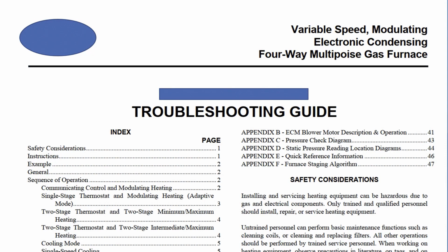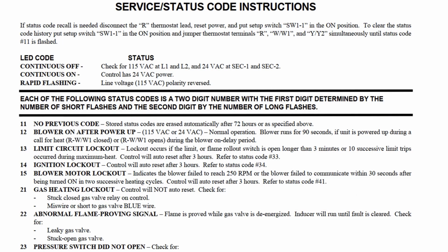Let's look at another example of a troubleshooting guide that we may need. This is for a variable speed modulating gas furnace. And this is the troubleshooting guide for that furnace, which gives us all of the alarms and fault codes that we might see and how to troubleshoot them and how to fix the situation. On the first page of the troubleshooting guide, you will find the various codes for the lights. All of your furnace boards are going to have lights on them, which will give you an idea of what is going on. The lights will usually flash short and long flashes so that you'll be able to determine what the fault code on the furnace is.